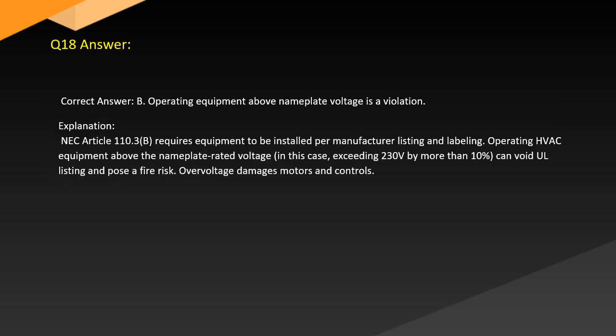Answer. Correct answer: B. Operating equipment above nameplate voltage is a violation. Explanation. NEC Article 110.3(B) requires equipment to be installed per manufacturer instructions, listing and labeling. Operating HVAC equipment above the nameplate rated voltage, in this case exceeding 230 by more than 10%, can void the listing and pose a fire risk. Overvoltage damages motors and controls.